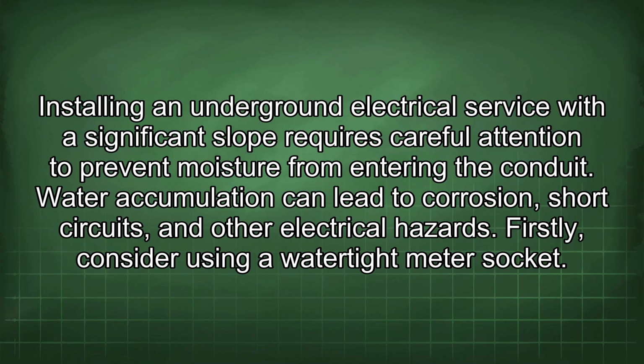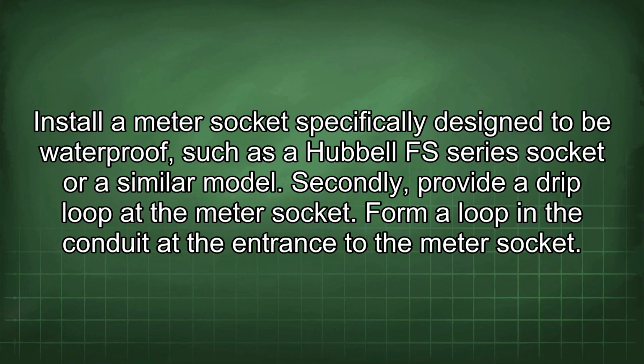Installing an underground electrical service with a significant slope requires careful attention to prevent moisture from entering the conduit. Water accumulation can lead to corrosion, short circuits, and other electrical hazards. Firstly, consider using a watertight meter socket. Install a meter socket specifically designed to be waterproof, such as a Hubbell FS series socket or a similar model.